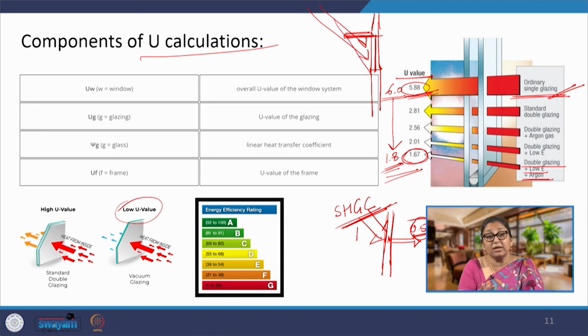There is no solar radiation that is incident, the SHGC remains the same, but the amount of heat that is transmitted inside is significantly reduced. So, SHGC becomes immaterial, or we could have multiplication factors, which is how the ECBC, Energy Conservation Building Code, works, and the calculation for the heat that is transmitted inside due to SHGC is calculated.